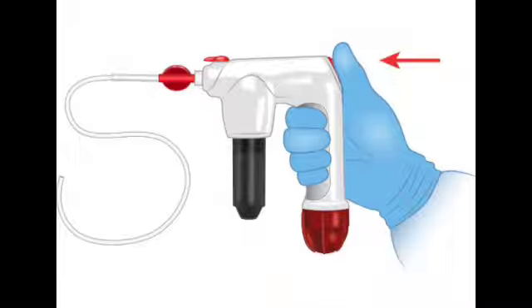We are dealing with high-pressure gas, tiny tubes, and a remarkably hostile wet environment. What happens if, despite the blow-drying and the air force field, a tiny amount of moisture seeps in and the catheter does get plugged? Well, if the powder turns into a solid block inside the tube, you might assume you could just hold the trigger down and use the high-pressure CO2 to blast the plug out. Yeah, like clearing a jammed pipe. That makes sense. It does make sense intuitively, but doing so is incredibly dangerous and strictly against protocol. Oh, yeah. The pressure could build up and cause the catheter to actually rupture. Or worse, it could suddenly release a violent, uncontrolled projectile of solid powder directly into the patient's delicate tissue.